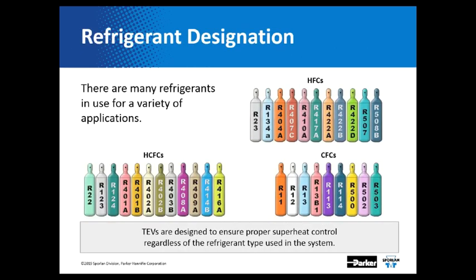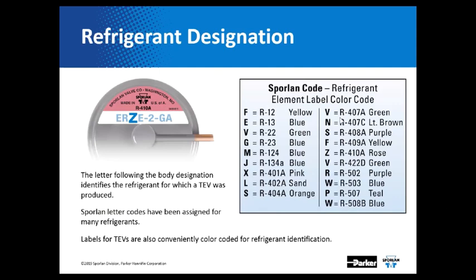Following the valve type in the nomenclature is our refrigerant designation. Refrigerants are abundant in the field — there are many different refrigerants in the industry for a wide variety of applications, and TEVs have to be designed to handle all these different refrigerants at the correct pressures and temperatures. As you can see, every refrigerant has its own different letter, and its own different colors as well. In this valve example — ERZE-2-GA — we know our valve type is ER, so Z is our refrigerant code. Looking at the code, Z is R-410A, and the color should be rose.